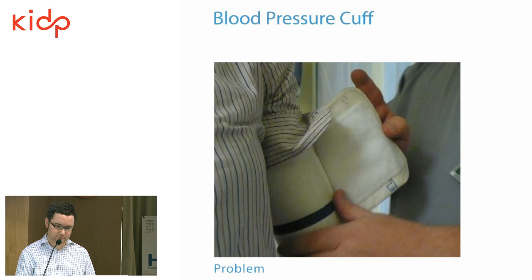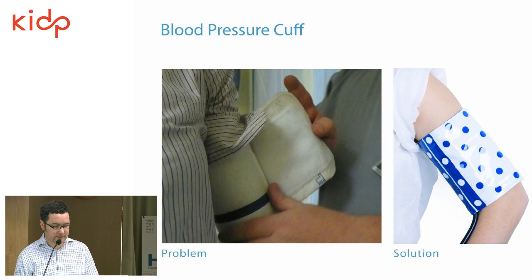So our solution was to use magnets within the blood pressure cuff, which means that the cuff itself is very easy to wipe clean, and there's no Velcro for bugs to live in.